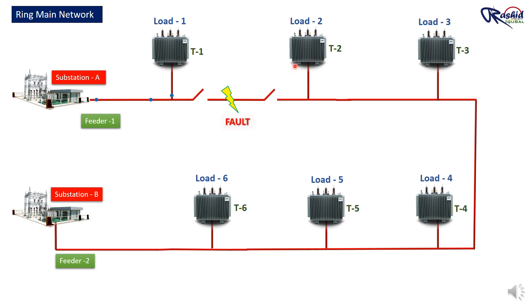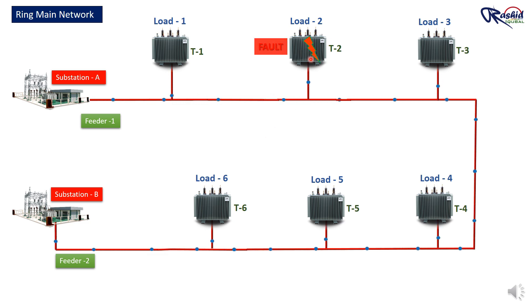When the breaker is off, all transformers after it will shut down. In this case, substation B will start supplying power through Feeder 2, so all transformers can still get power. This is one of the advantages of the ring network. Suppose there is a fault on the load or transformer side — we can turn off the power using the circuit breaker without affecting the feeder. This is another benefit of the ring network.